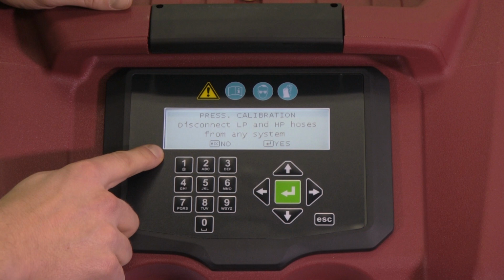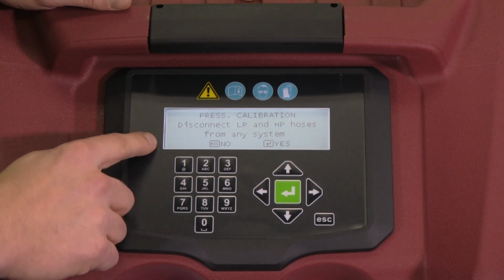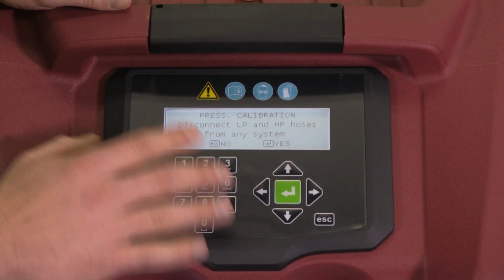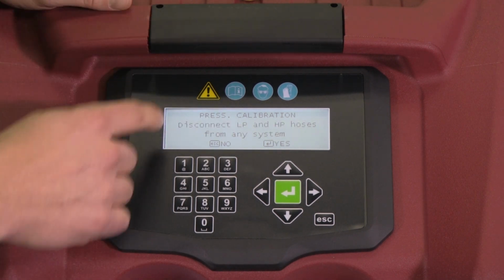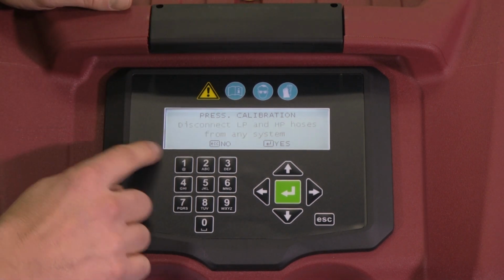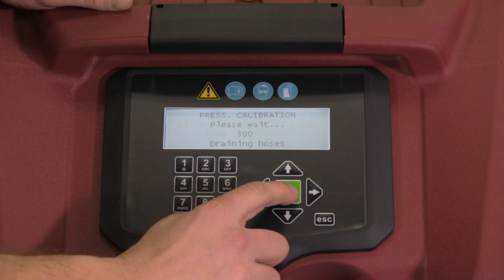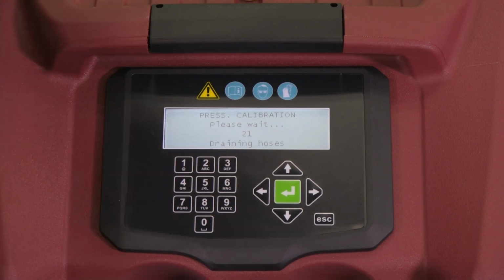At this point, it's going to ask me to remove or disconnect the LP or HP hoses from any system. They can remain parked to the parking couplers in the back of the unit, however, and say yes. So our initial hose drain is now winding down to the end, and we can continue with our process.